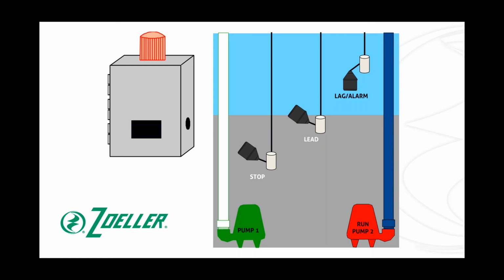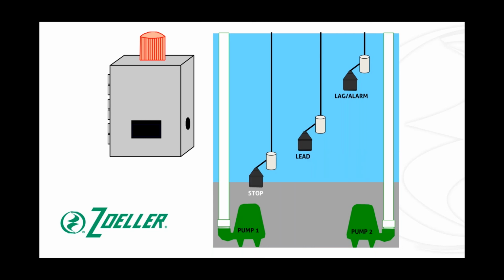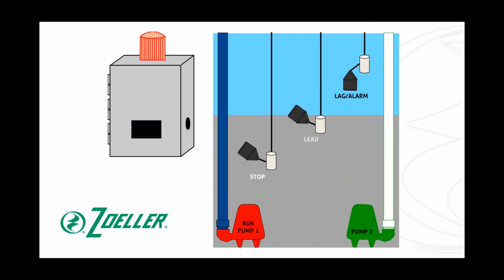So in this particular example right now, we see pump 2 is our lead pump, pump 2 is on, and it begins discharging water. Pump 2 is going to run and pump out water until that stop float drops out again. And when it does, it's going to shut off and it's going to be ready for the next pumping cycle. We'll go through it again. As water comes into this pit, the stop float rises, the lead float is activated, and pump 1, because pump 1 is our lead pump this time, is going to come into action.